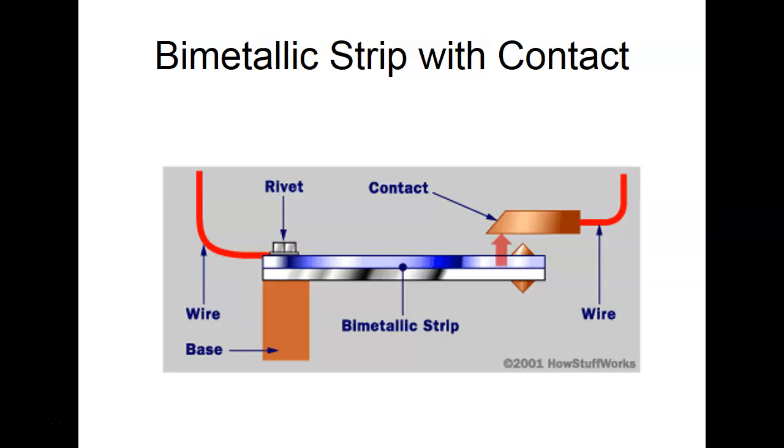So we can use bimetallic contacts. So this is the sensor that we normally use inside of the small motors. Most motors, even very small fractional motors, have to have what we call overload sensors in them. I was going to say, on these motor starters that we use over here, you have the thermal sensors on there. This is a single phase motor. It's a three speed motor.